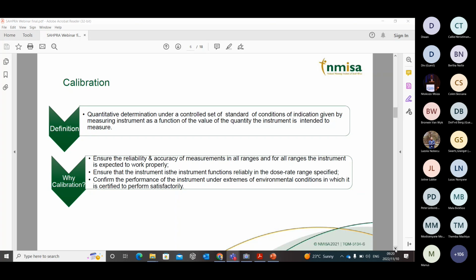And that standard is also used to participate in the international comparisons to ensure the degree of equivalence to the international community. And then the other question that we need to ask ourselves is, why do we have to calibrate the instruments that we use? We need to calibrate them in order to ensure the reliability and accuracy of measurements in all ranges that the instrument is expected to work properly. We also need to calibrate our instrument to ensure that the instrument functions reliably in the dose range specified.